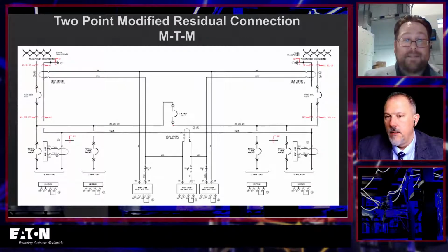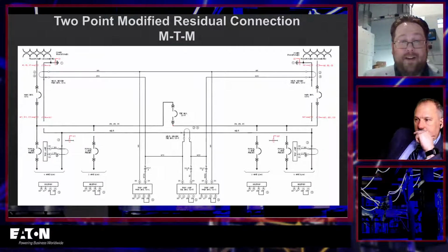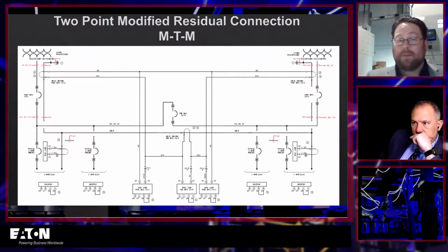And in this instance, with the residual connection, we have now multiple sensors or multiple CTs feeding back into those trip units to make that work ultimately. And we're going to test the coordination of the system. So I'm going to see that happening also to ensure that the tie breaker and the main breaker are actually coordinated properly from a ground fault perspective.